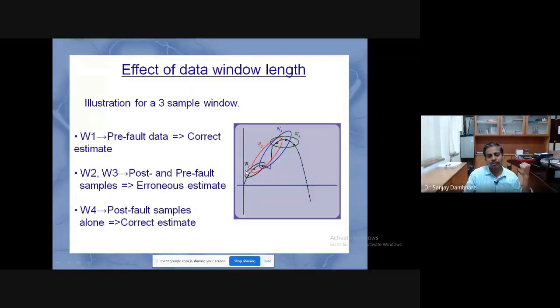Window 1 is enriched with pre-fault data, and window 4 is enriched with post-fault data. Suppose there is a fault; window 2 or window 3 is enriched with both post-fault and pre-fault data. So you can expect erroneous estimation of the phasors in that particular period, while in other periods the phasor estimation algorithm will estimate the correct value. These are some of the hardcore issues, and a lot of research is being done in this direction.